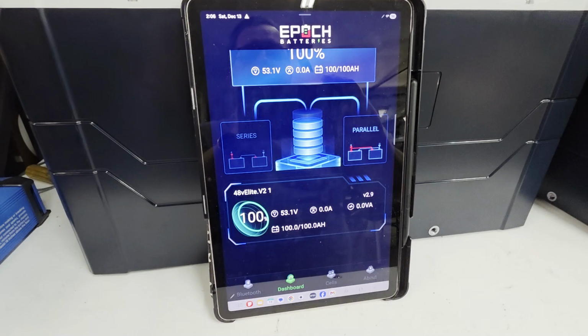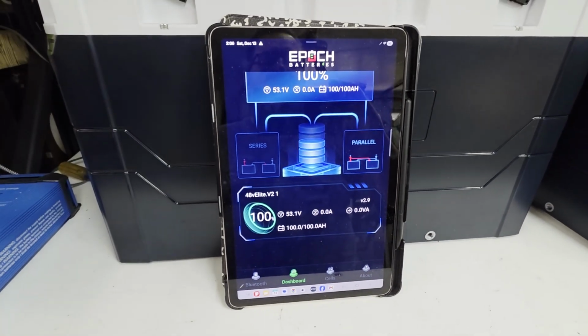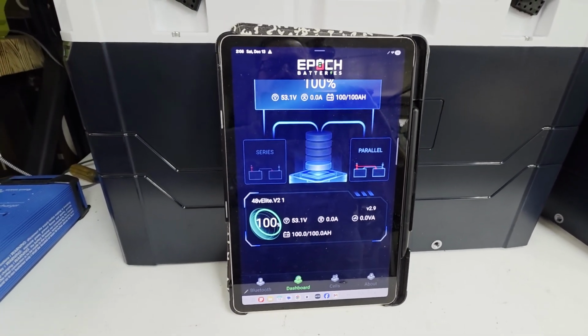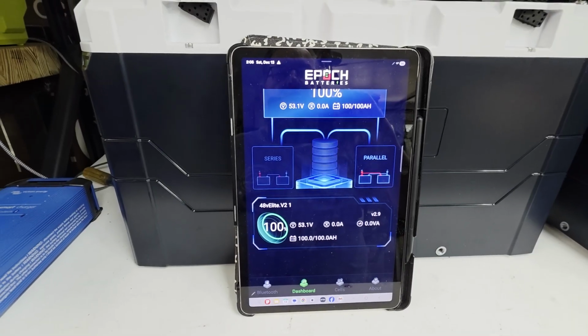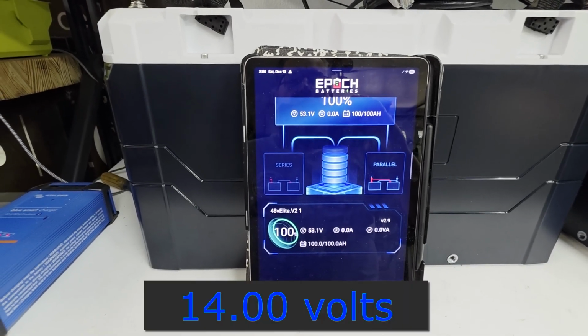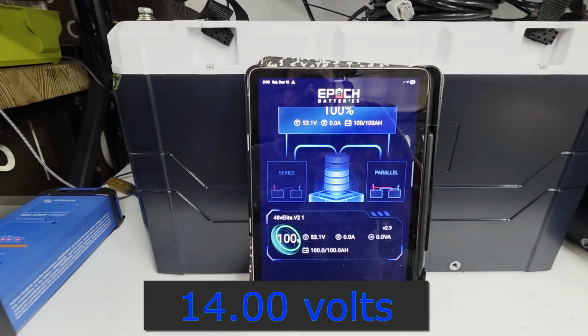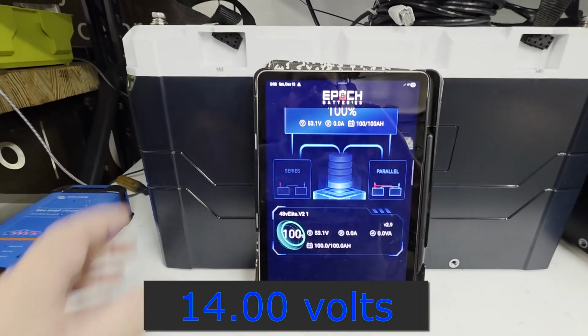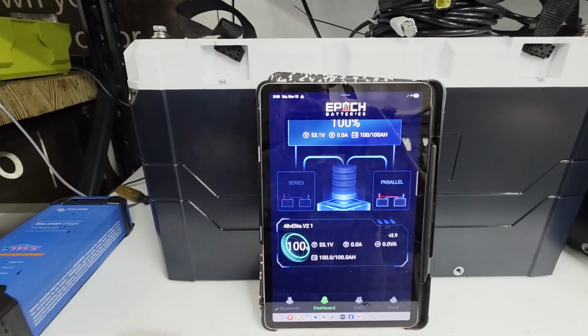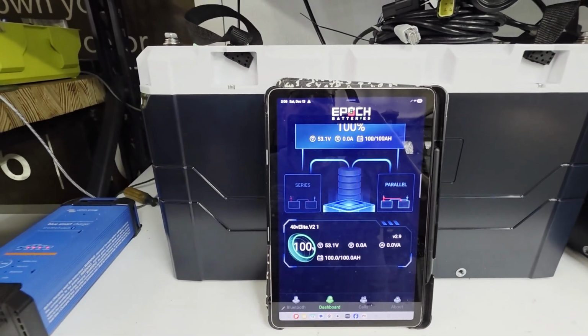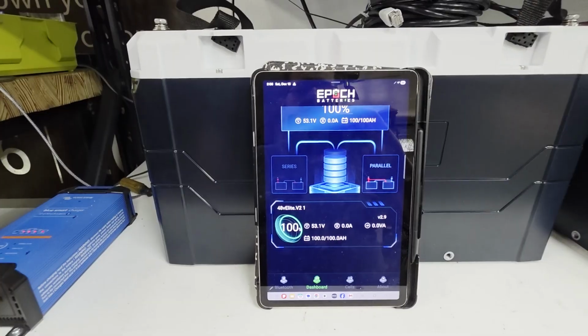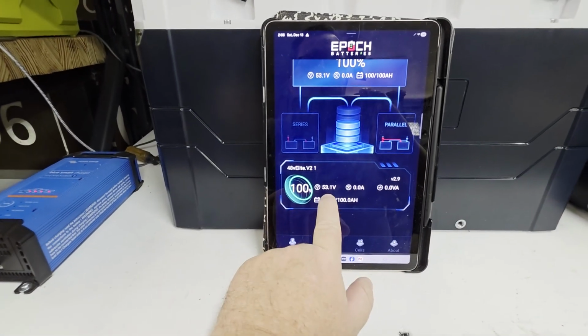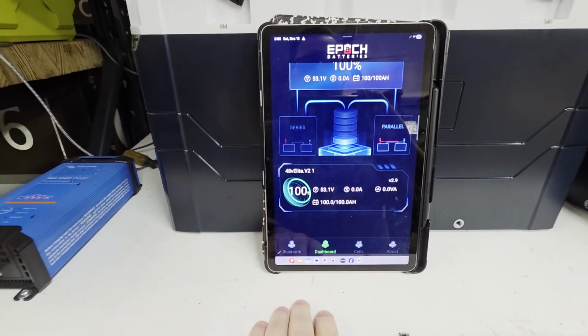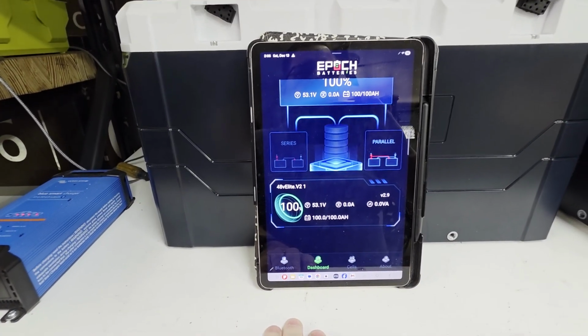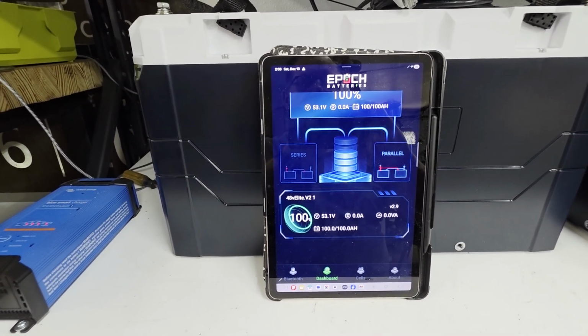Remember that the new CVL will be 14 volts, not 14.2. You should see it go to 100% when it hits 14, after roughly 15 minutes per battery, up to a cap of 2 hours if you have a lot of batteries. So for a 2-battery system, maybe after roughly 30 minutes you'll see it hit 100%, but your voltage will only rise to 14 volts, or 56 volts on a 48 volt, or 28 volts on a 24 volt battery.